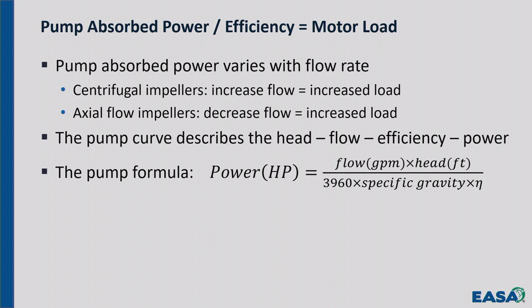But unless you're knowledgeable enough, not expert, in looking at the pump flow conditions and comparing it to the pump curve and saying, hey, if you've got this flow and this head, you're going to need that amount of power, and that motor ain't got it. It's not our problem. The problem is with the pump. If you don't have that, you're just at a loss. You have nothing to tell your customer. So we need to be able to understand a little bit about pump curves.